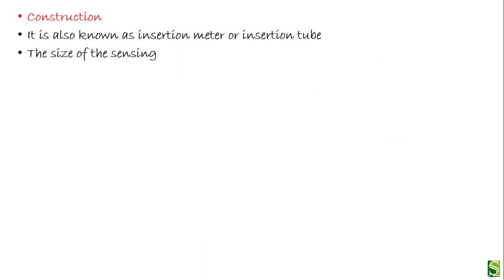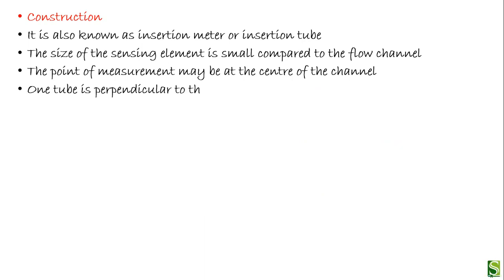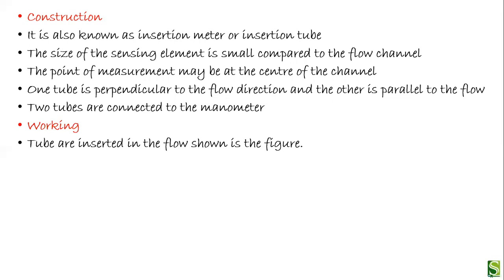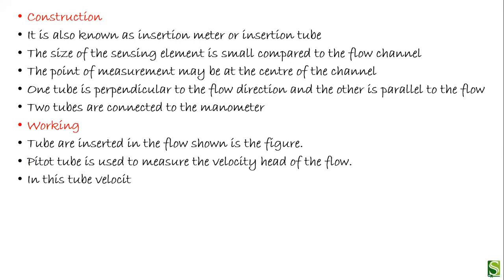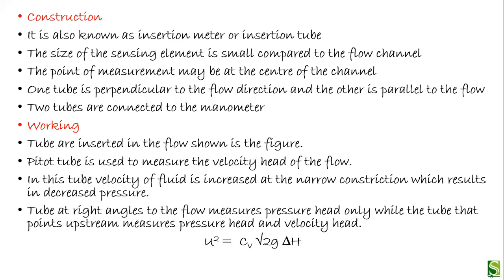The size of the sensing element is small compared to the flow channel. The point of measurement may be at the center of the channel. One tube is perpendicular to the flow direction and the other is parallel. Both tubes are connected to the manometer. The tube is inserted in the flow as shown in the diagram. The pitot tube measures the velocity head of the flow. The formula used is: u² = Cᵥ√(2g·Δh), where Cᵥ is the coefficient of the pitot tube.